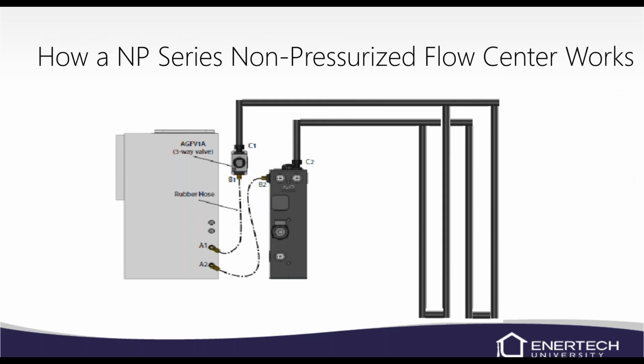Basically, how a non-pressurized flow center works: the flow drops into the top of the tank. If there's any air in the water that comes back, the air will go to the top of the tank and be eliminated through that gas cap type cap. Then it actually sucks water out of the bottom of that tank. There's a dip tube, and it'll go up and through the pump, out through your valve, into the unit, and back through.